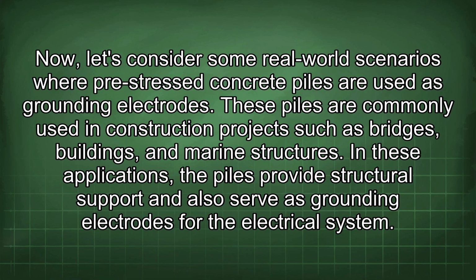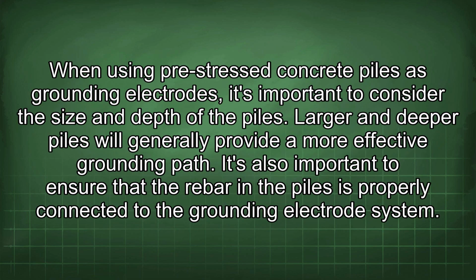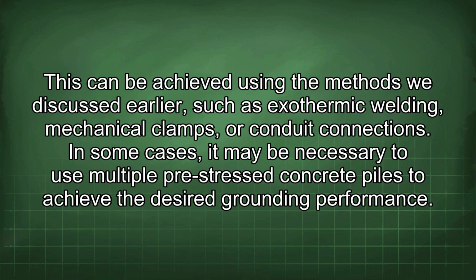In these applications, the piles provide structural support and also serve as grounding electrodes for the electrical system. When using pre-stressed concrete piles as grounding electrodes, it's important to consider the size and depth of the piles. Larger and deeper piles will generally provide a more effective grounding path. It's also important to ensure that the rebar in the piles is properly connected to the grounding electrode system. This can be achieved using the methods we discussed earlier, such as exothermic welding, mechanical clamps, or conduit connections.